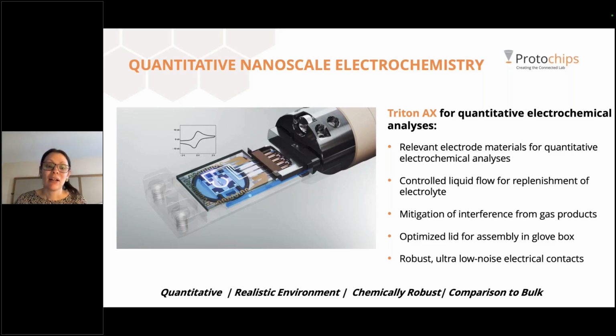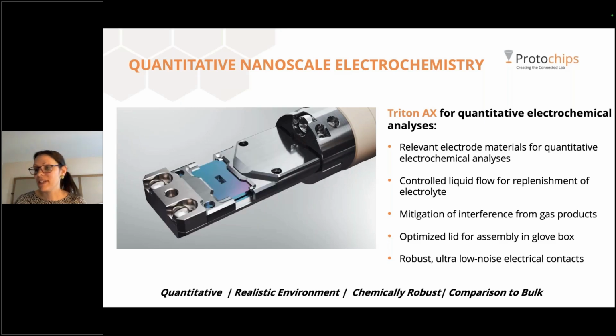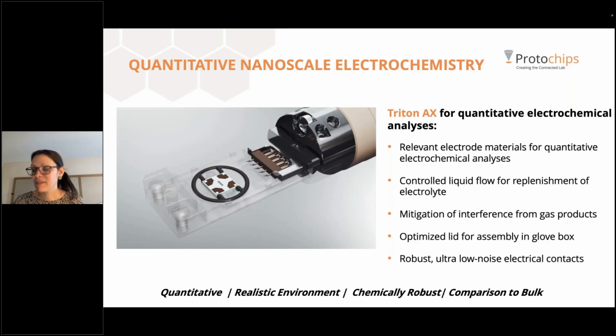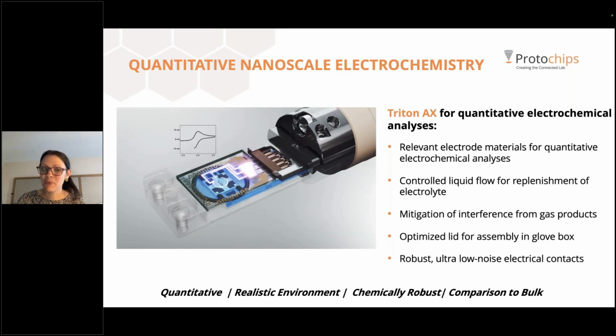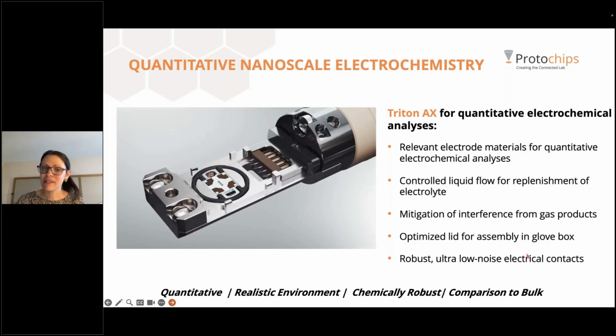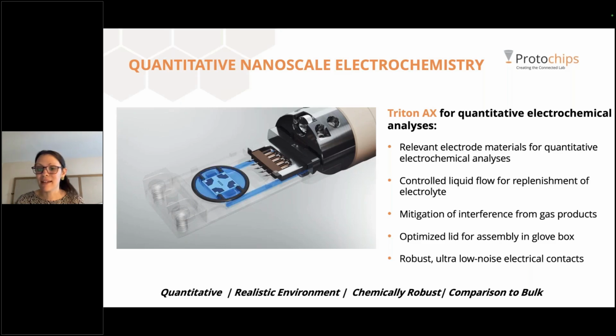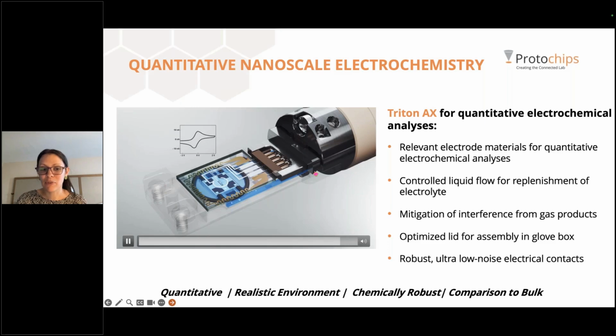which is very comparable to what's used on the bulk scale. The design of the chips and the design of the holder ensure controlled liquid flow for the replenishment of the electrolyte. You have to walk a very fine line with liquid electrochemistry and make sure you have enough electrolyte for good signal to noise, but you also want to control the thickness of it for better imaging resolution. With our chip designs and our holder design, you're able to do that. There's also mitigation of the interference from gas products. Some of these experiments produce gases, bubbles, and sometimes you accidentally produce bubbles. You're not supposed to. If you do, you need to be able to remove them, which the design of the chips here enables.